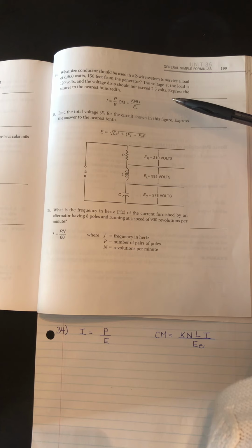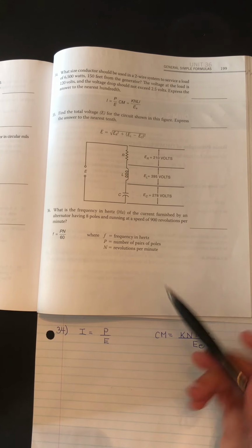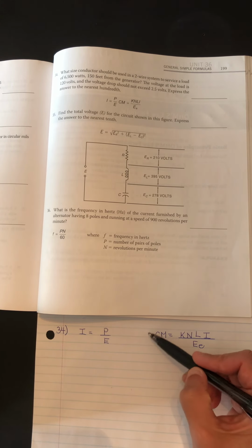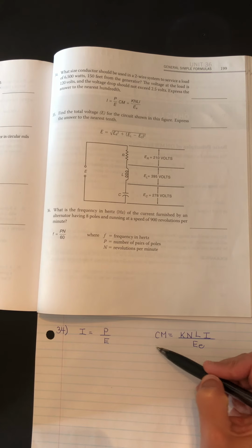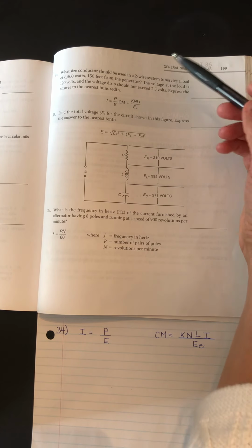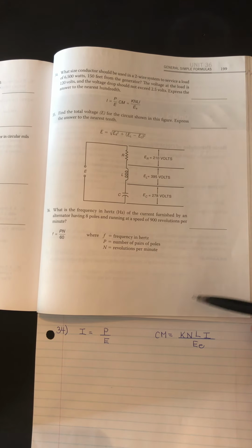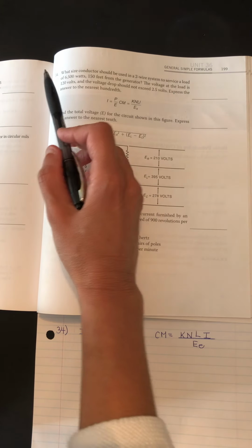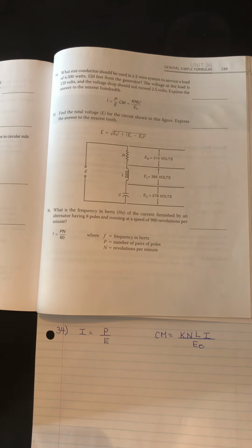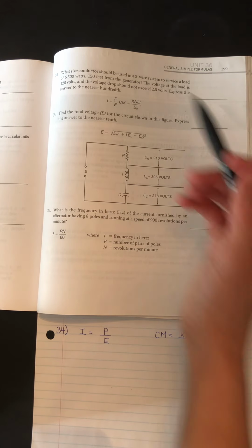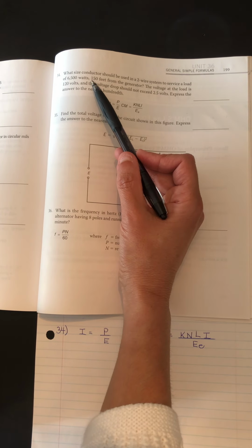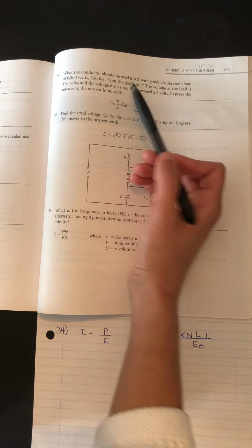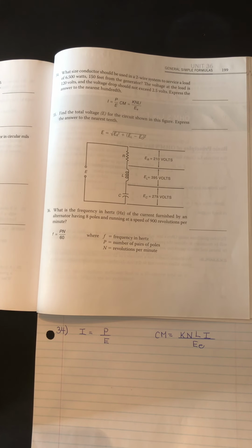What size conductor? So that means solving for the number of circular mills. Okay, it's a two-wire system, so N is 2. Remember, K is 10.8. We have a load of 6,500 watts. And we have the L value is 150. Okay.